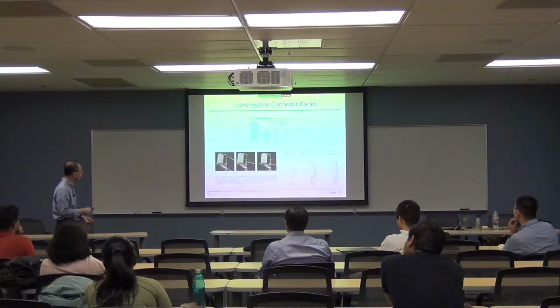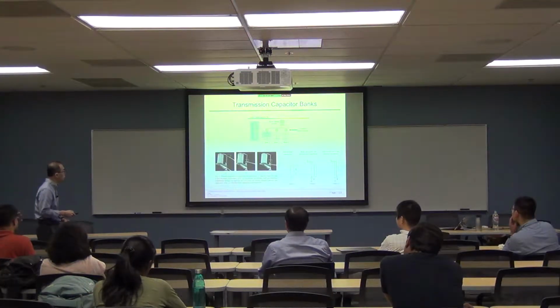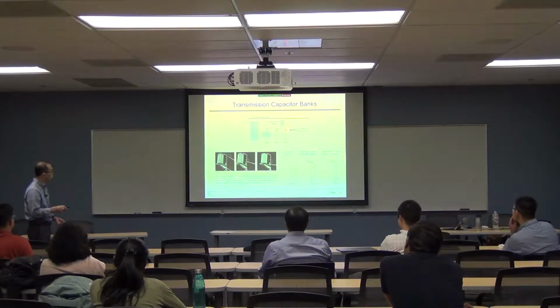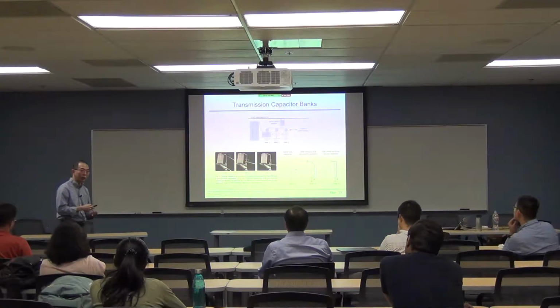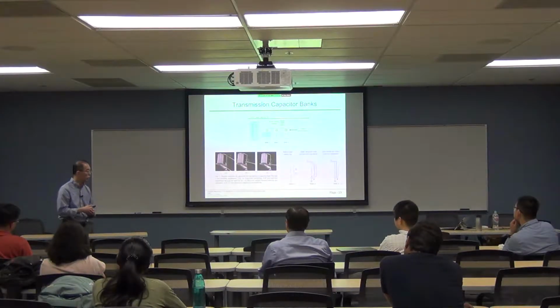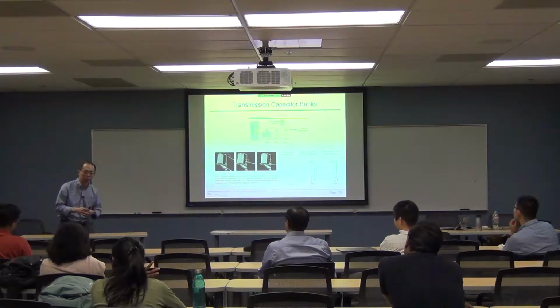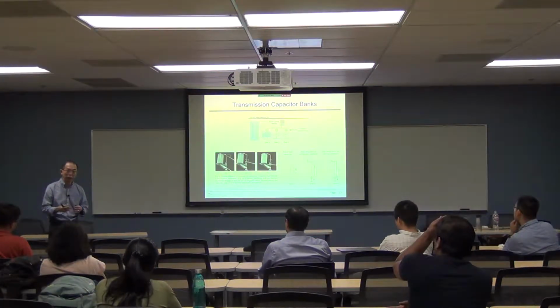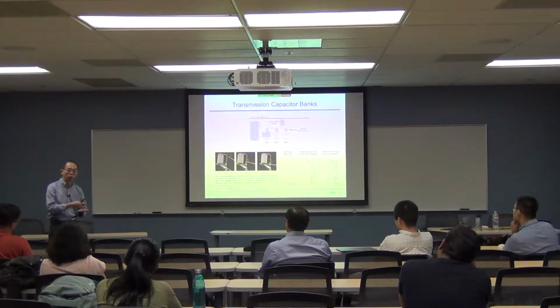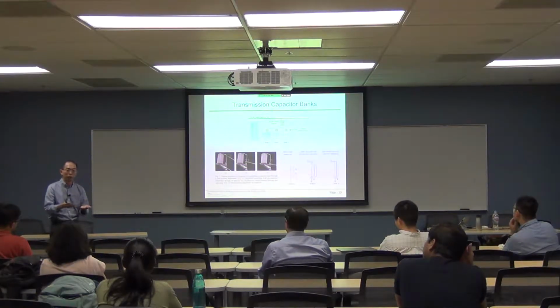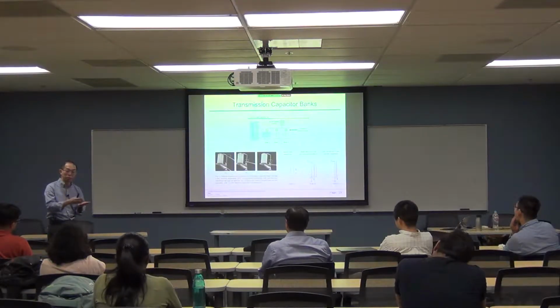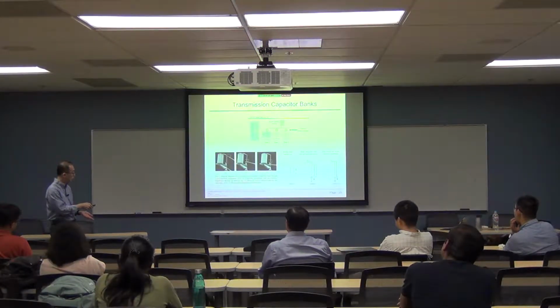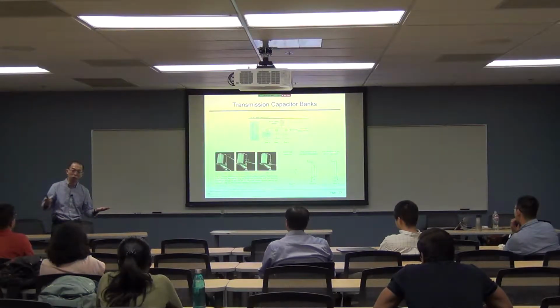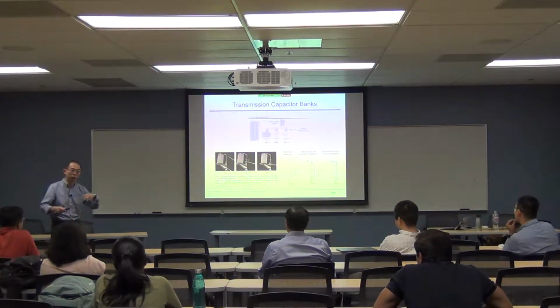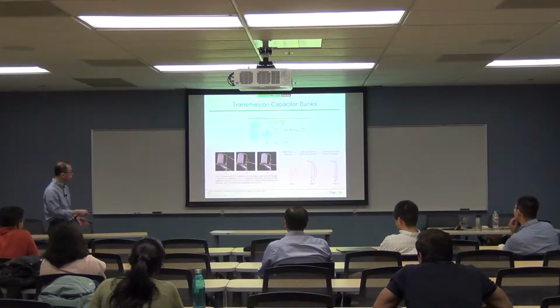What we are after in this view is to assess the health condition of the capacitor circuit switcher. Now if you have been working around capacitor banks for some time, you would know that a capacitor can be energized with a circuit switcher that has no control, just close energized, but it can also be energized using a pre-insertion element, such as this one I'm talking about, or using synchronous closing control, which is another strategy. But let's look at this one first.